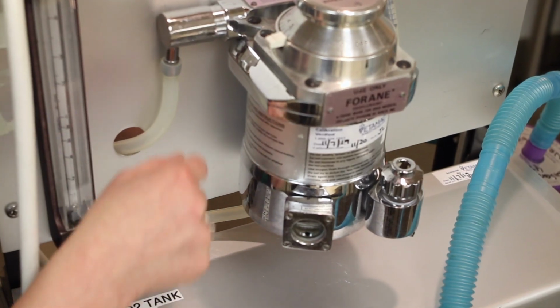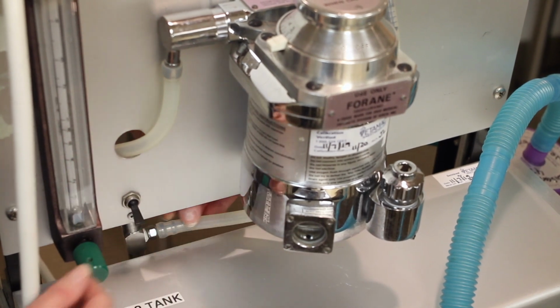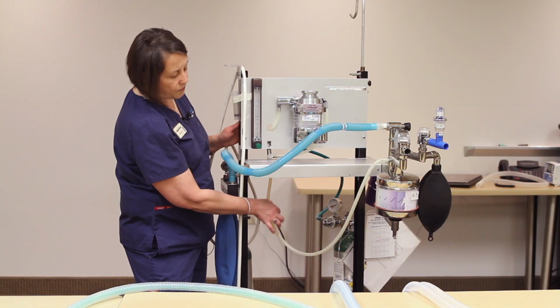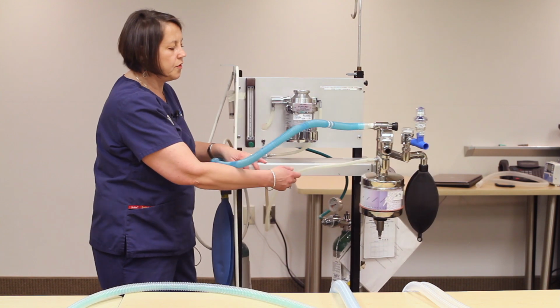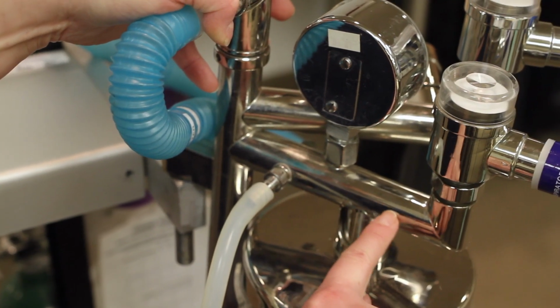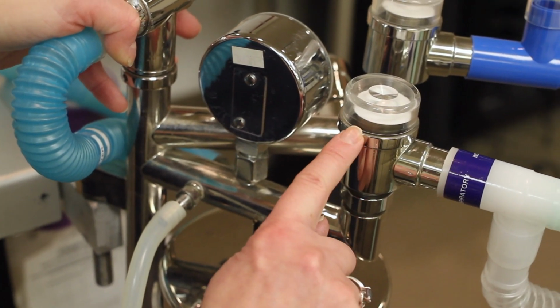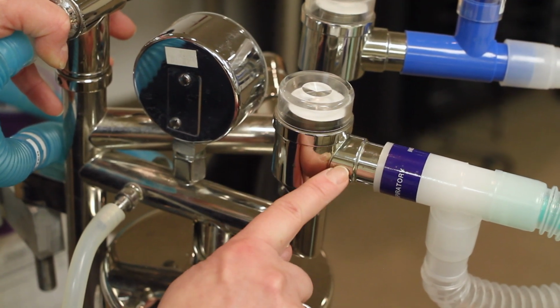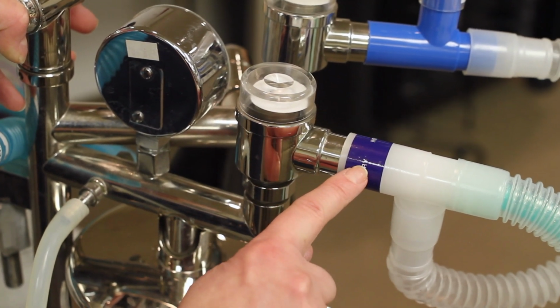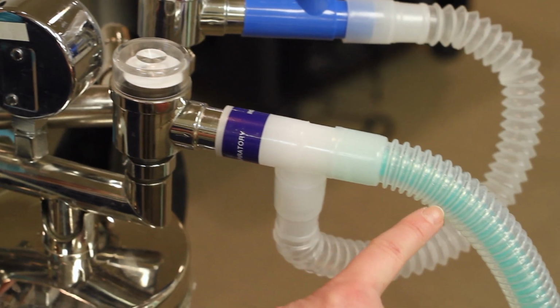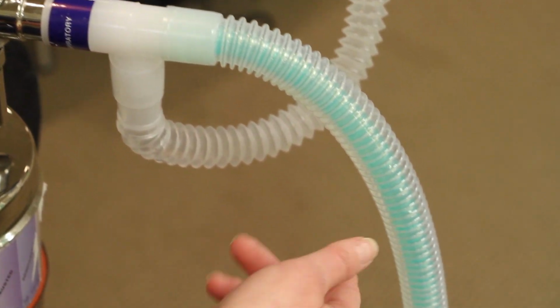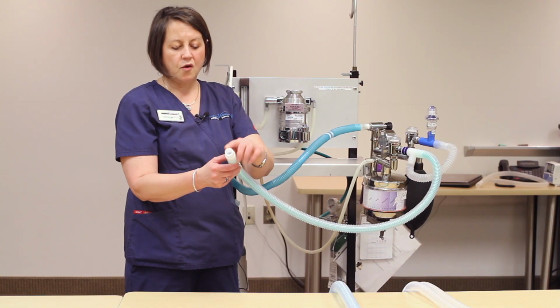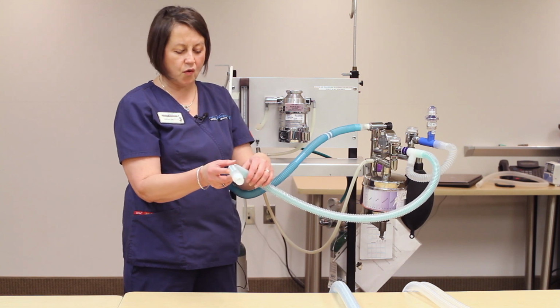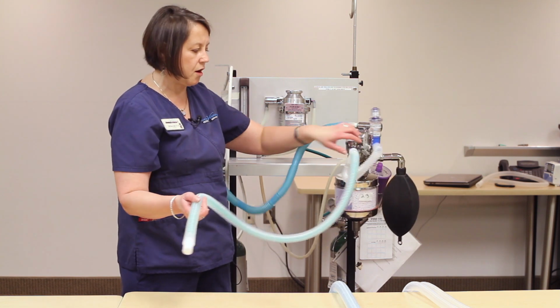Then it comes out of the outlet and through this tube, down through this tube, traveling in this orientation, through this one-way directional valve. You can see the arrow pointing there — that's the inspiratory side. The gas goes through the inner teal tube as the animal is inhaling. Once they exhale, the gas goes through the outer tubing.